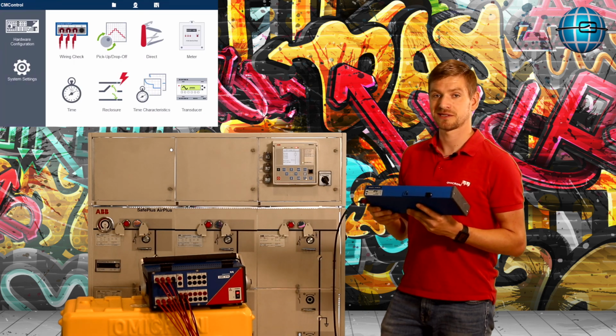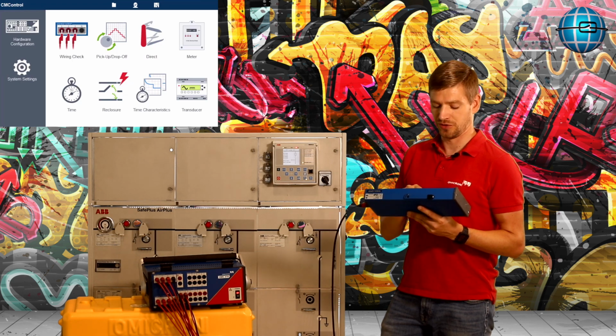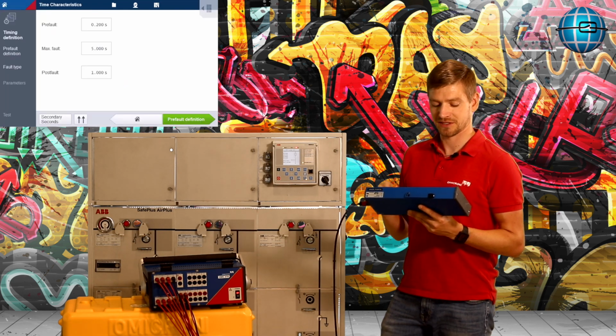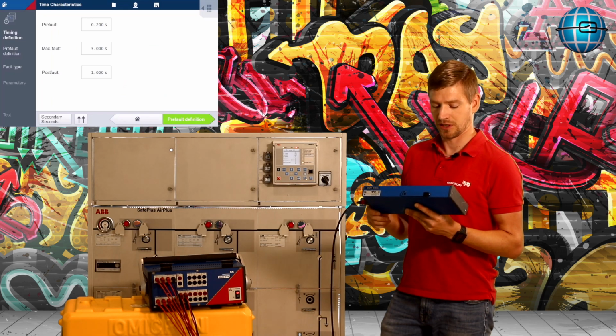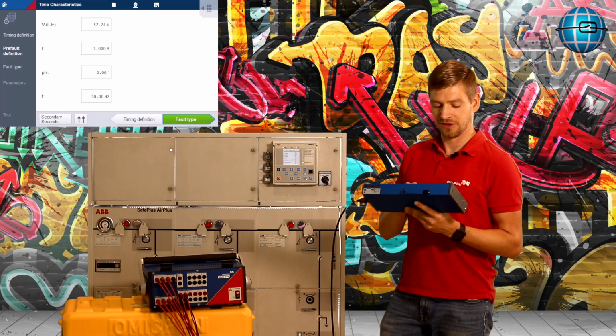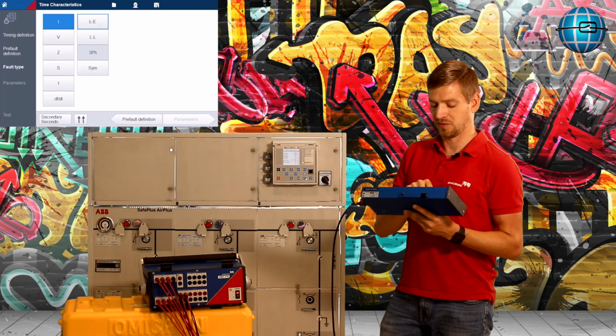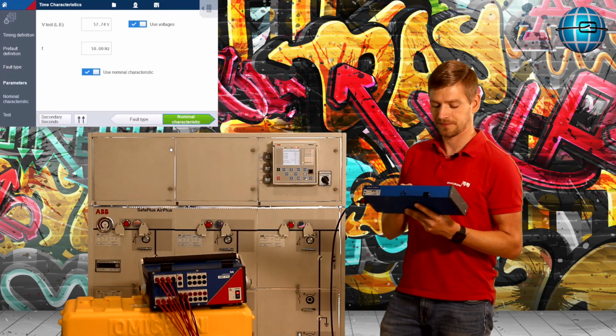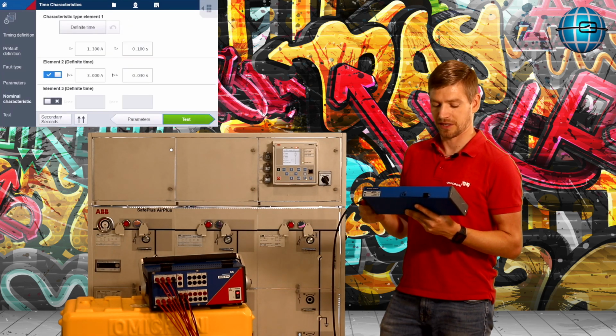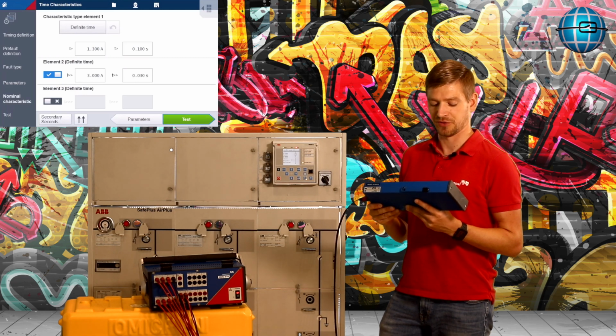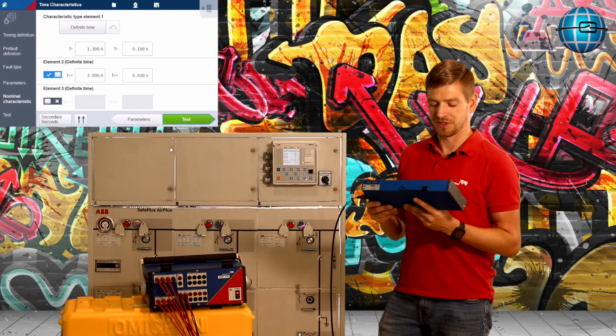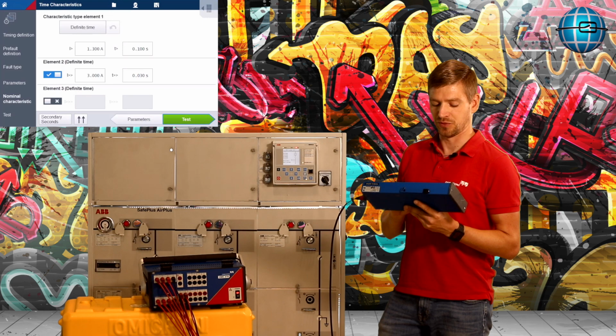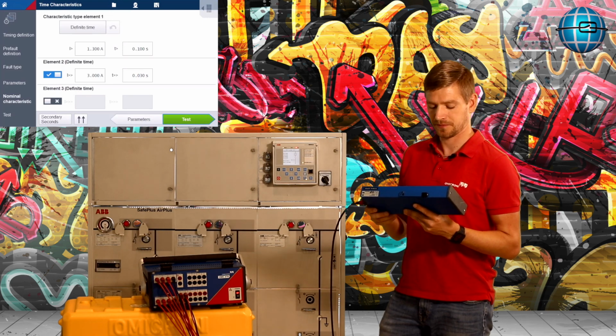And the next short test I would like to show you is a quick overcurrent test. Therefore, we have here this time characteristic tool. Go in the fault configuration. In this case, I will use a 3-phase fault. And here I can configure my two-stage overcurrent protection: 1.3 amp at the first stage and 3 amp at the second stage.